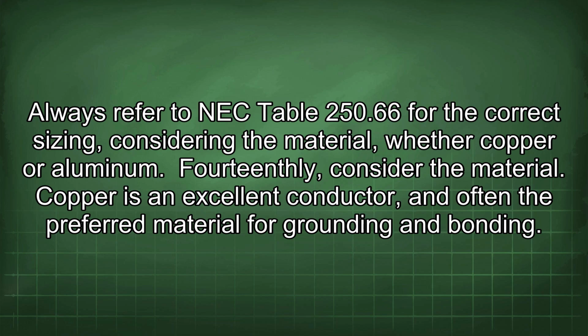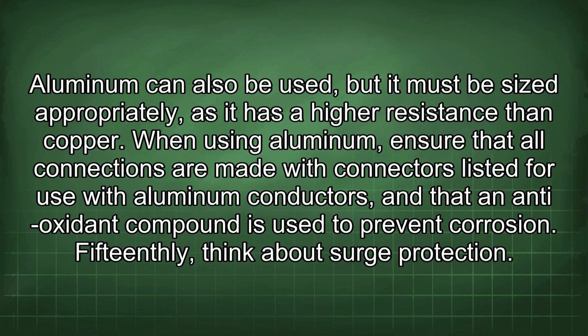14thly, consider the material. Copper is an excellent conductor and often the preferred material for grounding and bonding. Aluminum can also be used, but it must be sized appropriately, as it has a higher resistance than copper. When using aluminum, ensure that all connections are made with connectors listed for use with aluminum conductors and that an antioxidant compound is used to prevent corrosion.